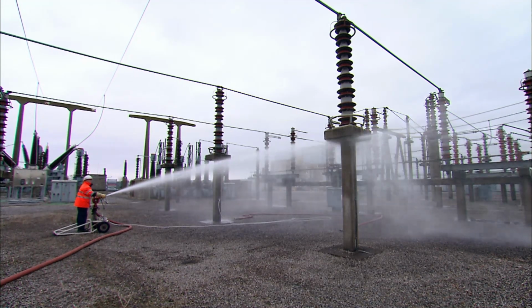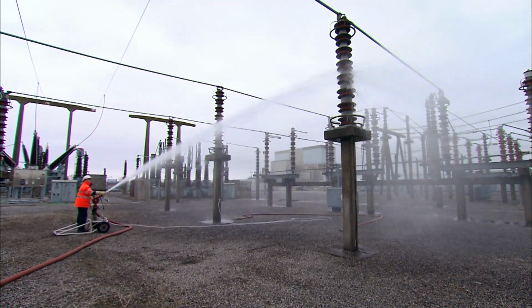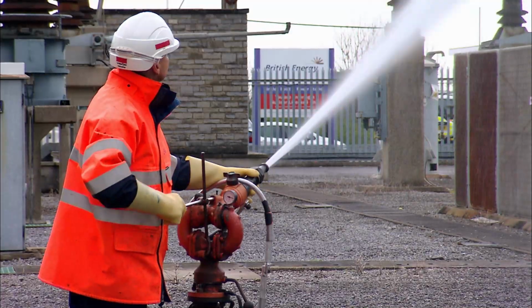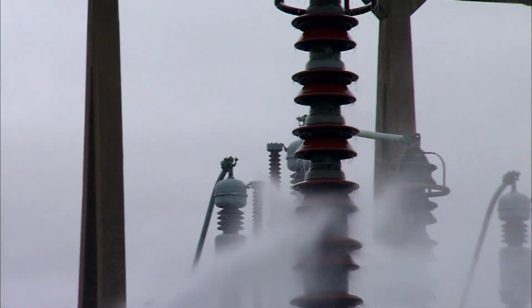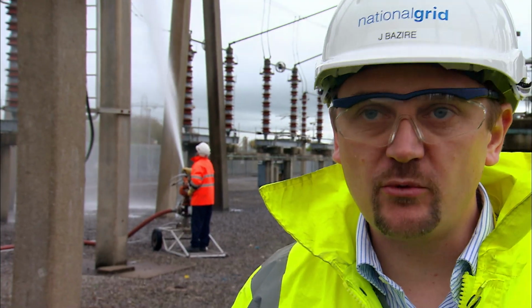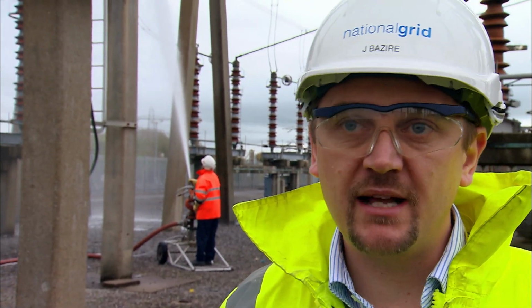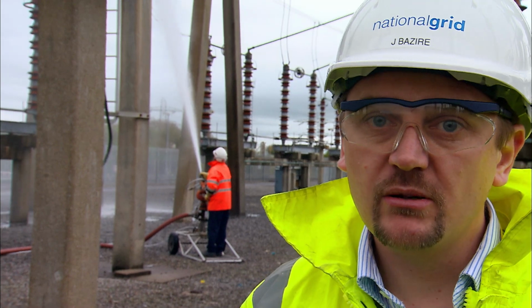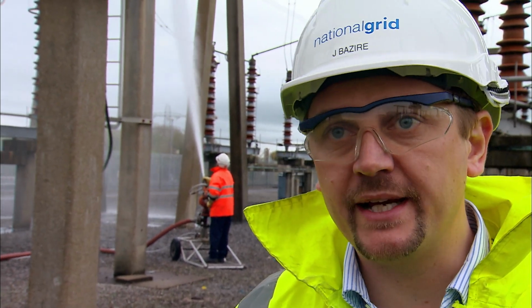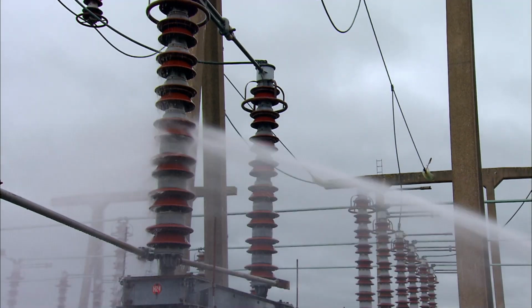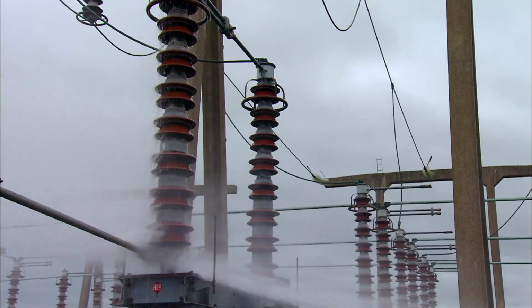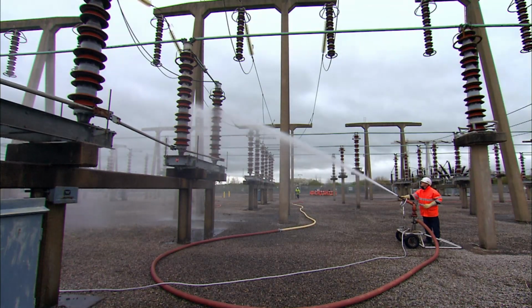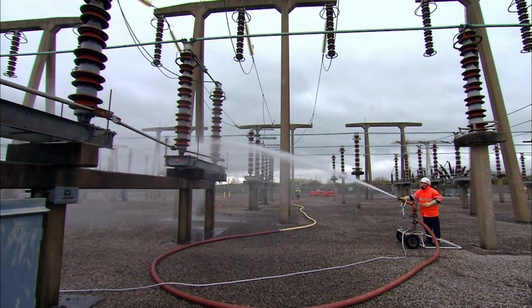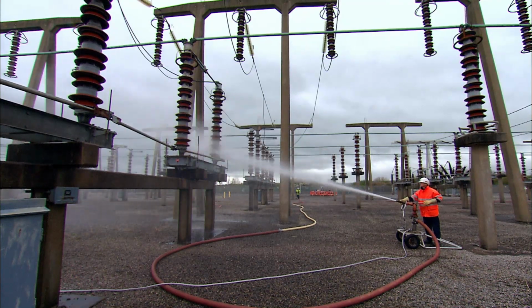For most of us, squirting salty water over a high-end electrical installation would be a high-tension activity. For the Hinkley Point team, it's become a regular appointment. Well, it's done on a routine basis. Throughout the winter months, between November and March, we tend to do this washing once every week. But in the summer months, the problem doesn't seem such a big issue, so it's done once every 2 weeks. And time has taught us that that seems to be about the right level of washing that's required.